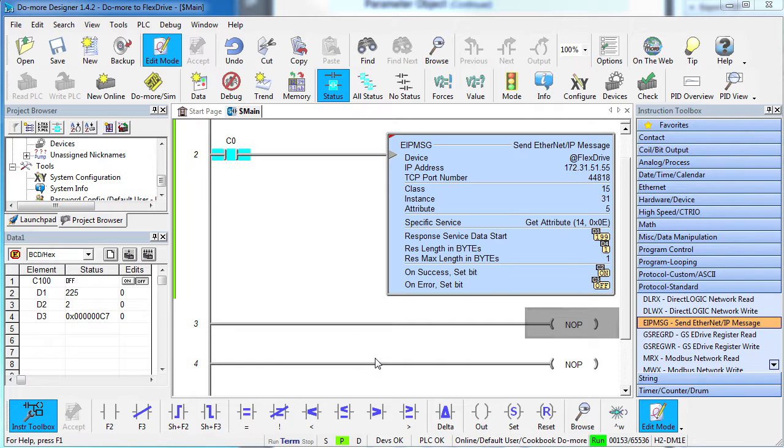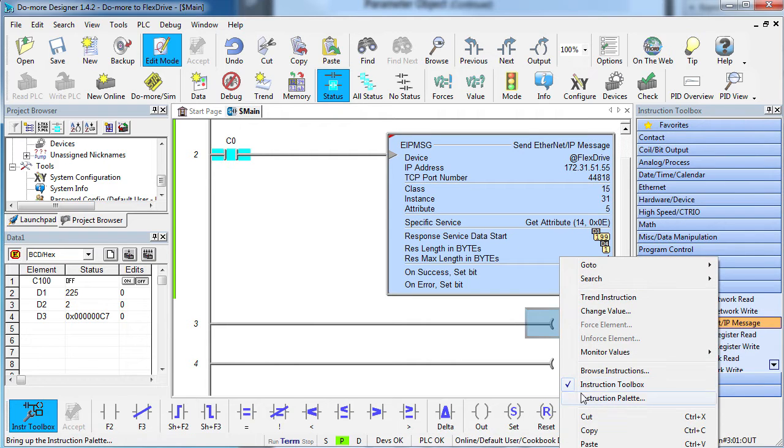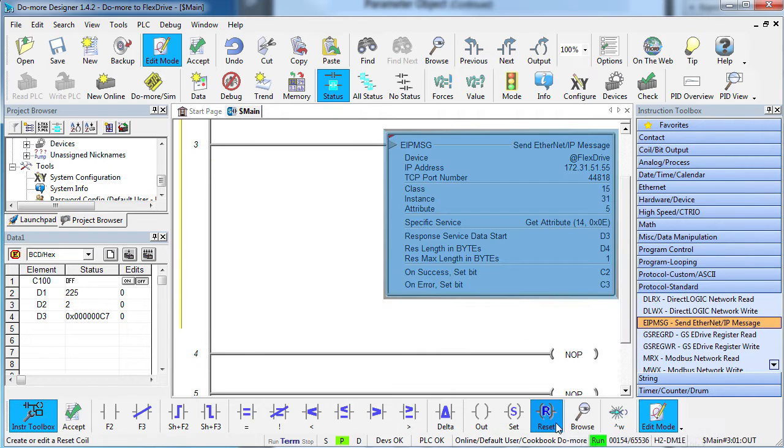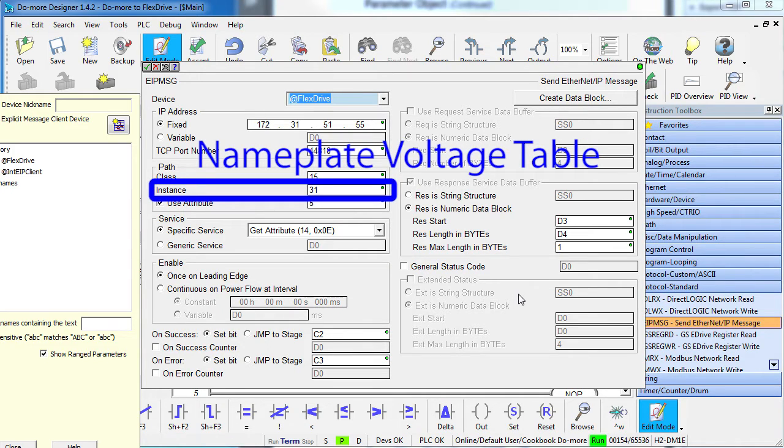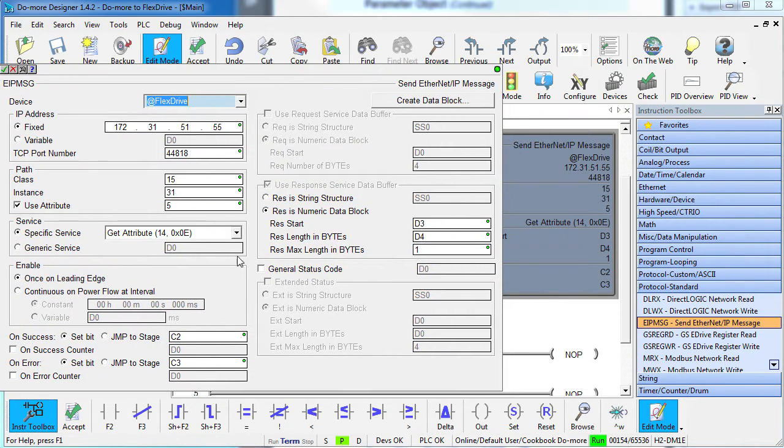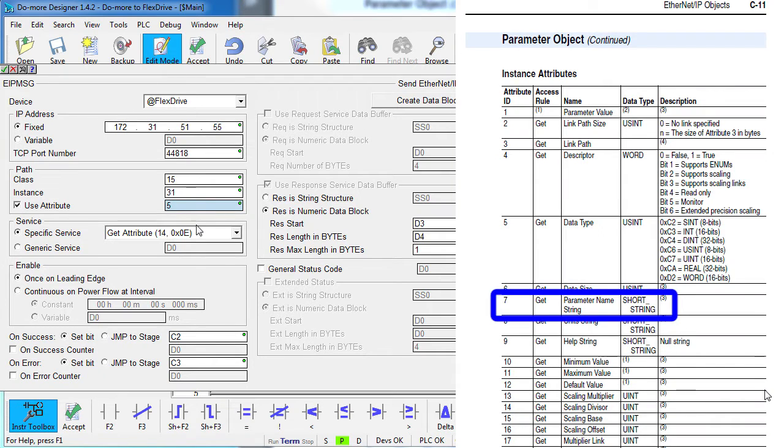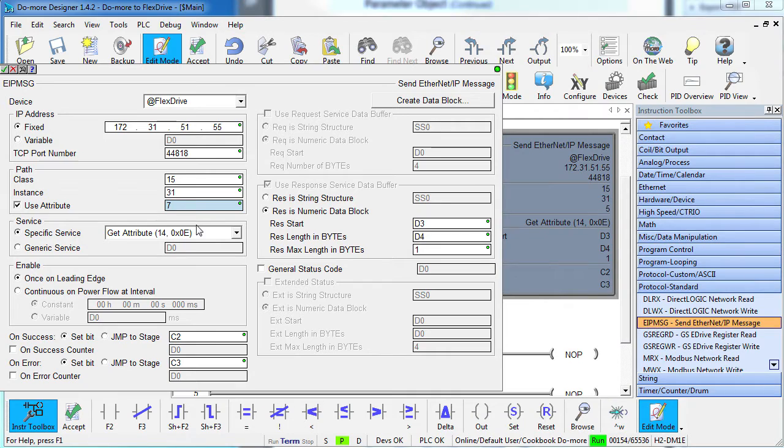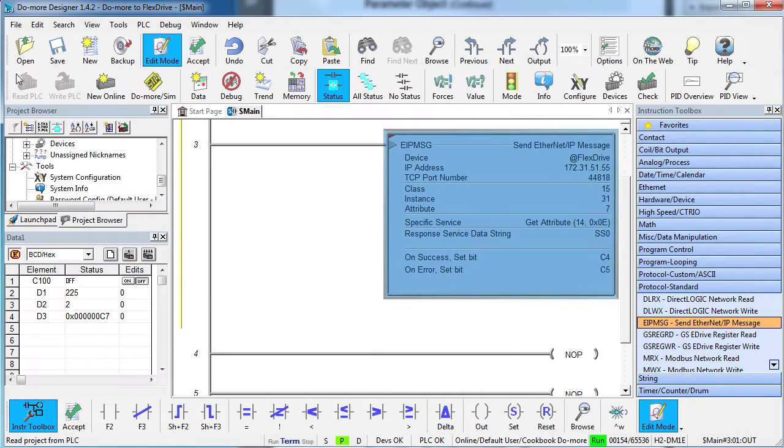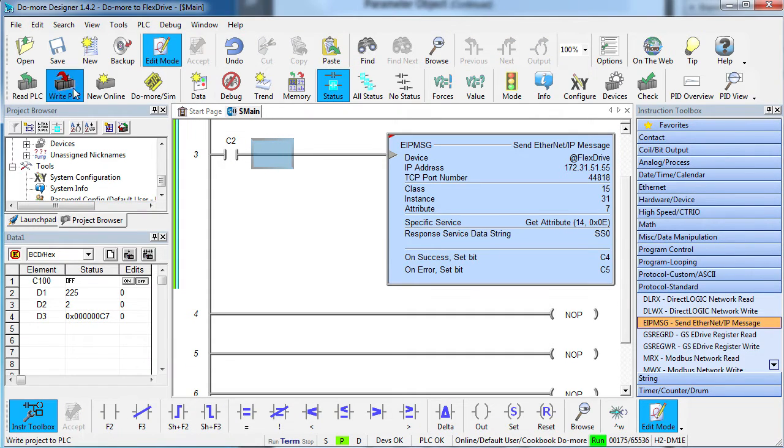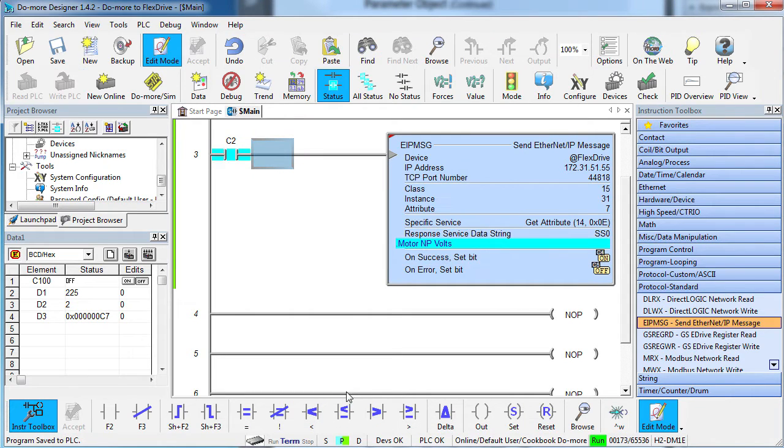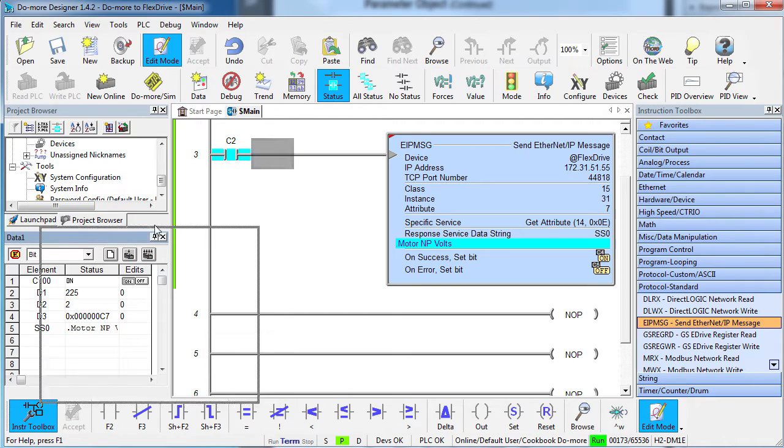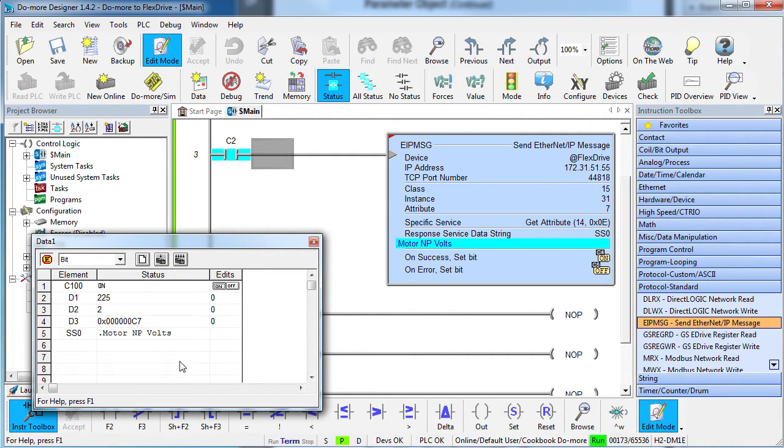Let's do another one. Let's get the name of this parameter. Again, it's almost identical to what we just did so we will just copy this instruction. Same class or group of tables, same instance or table number, the only difference is now we want a different row of the table or attribute of the parameter. We see back in Appendix C that the name of the parameter is attribute number 7 and that it's a short string. So we put 7 here and put the result in a string structure. Change the success bits and we're done. Trigger this one on the success of the previous one. Accept everything and write it out to the DoMore. Add our new string to the data view. Toggle the control bit and we see that the name of this parameter is Motor Nameplate Voltage. Awesome!